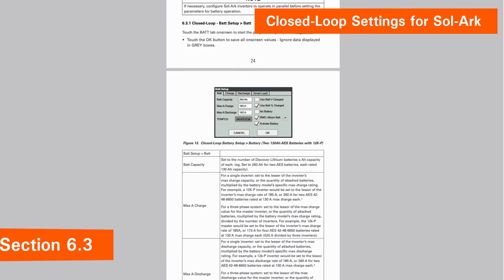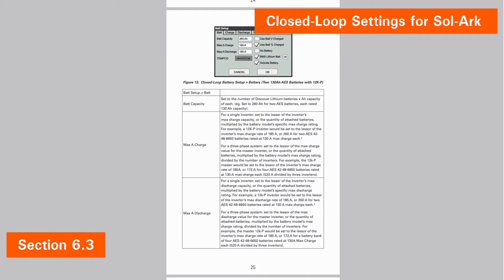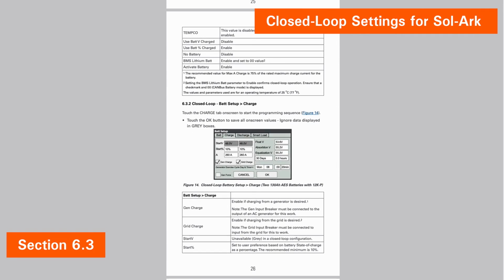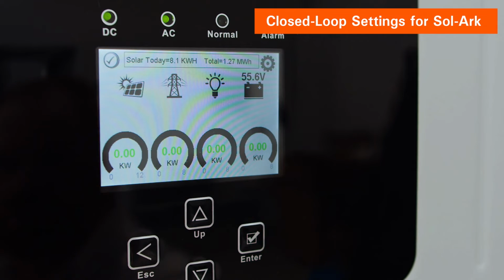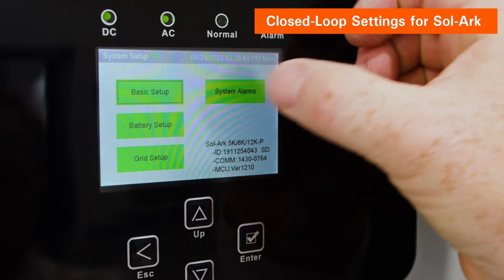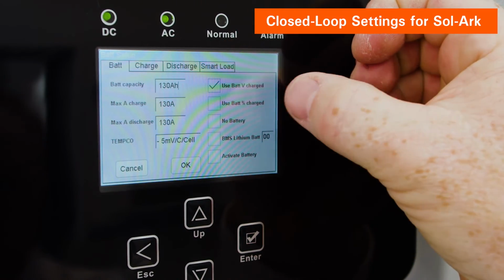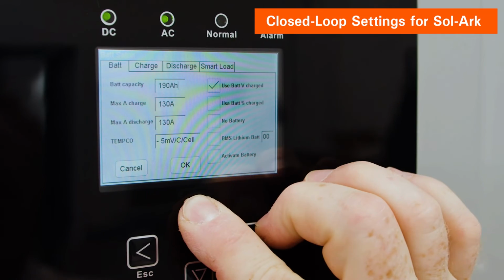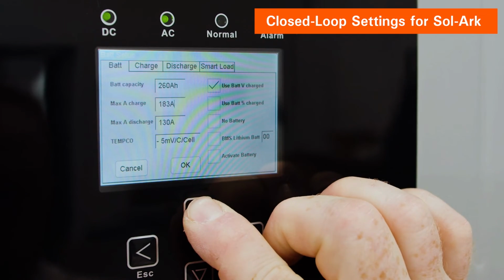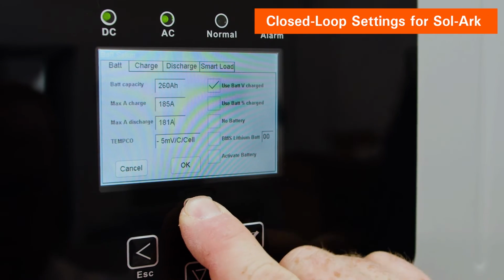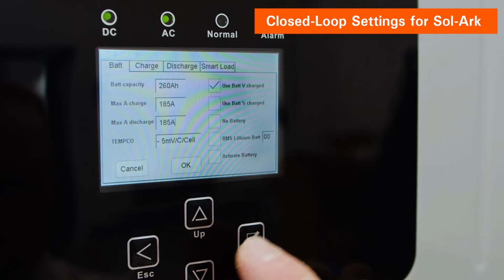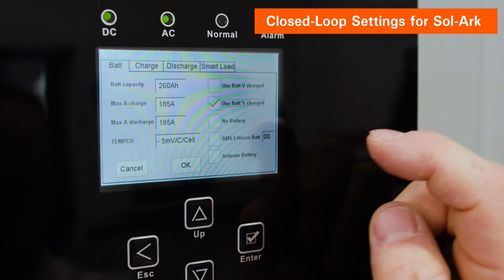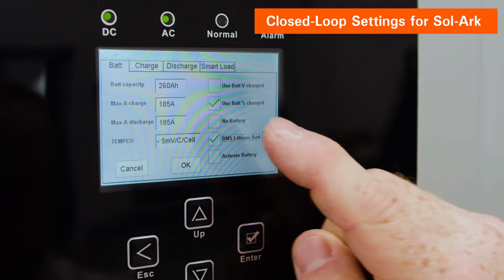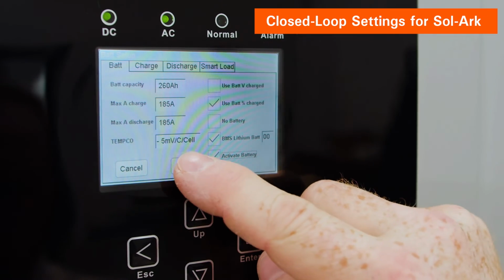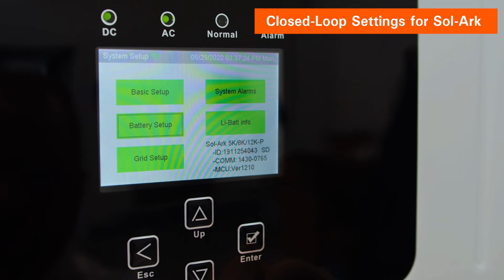You can refer to section 6.3 of the LYNK II Sol-Ark user manual. You'll find the list of the Sol-Ark closed-loop settings. Using the touchscreen and keypad on the inverter, navigate from the system setup to the battery setup screen. On the BAT screen, set up the parameters for battery capacity, max charge amps, and max discharge amps. For the safe and proper operation of the system, we recommend enabling both the BMS Lithium BAT and Use BAT percentage charged function. Remember to press the OK button to save your changes.